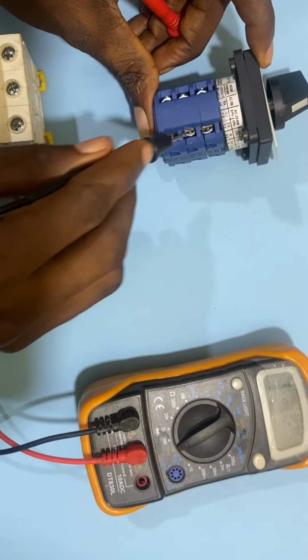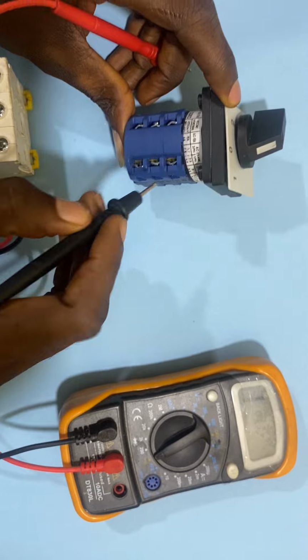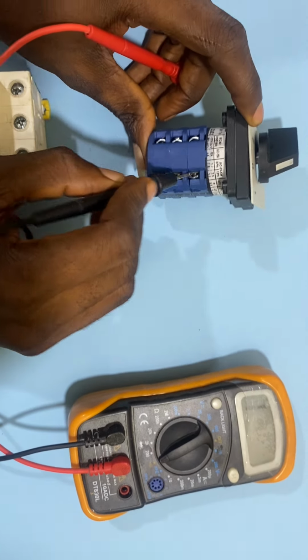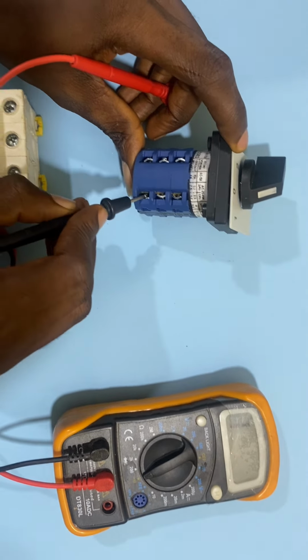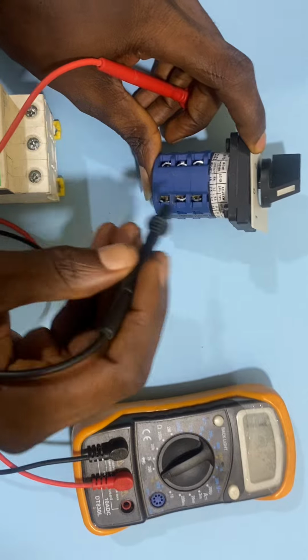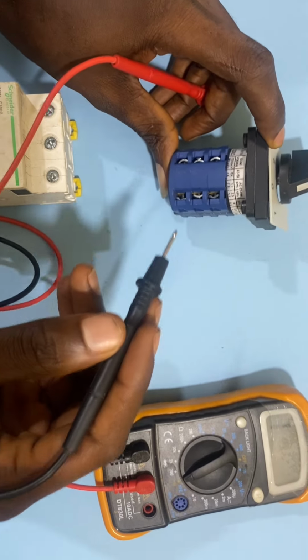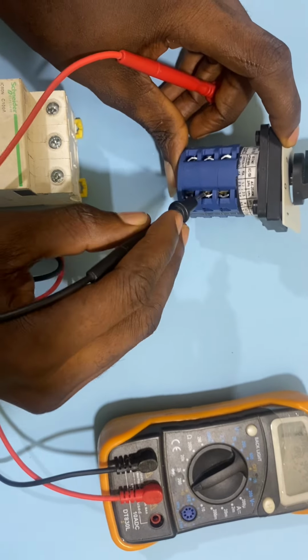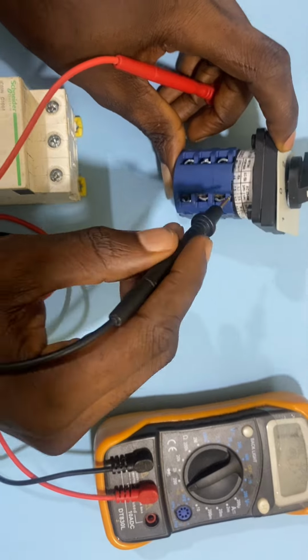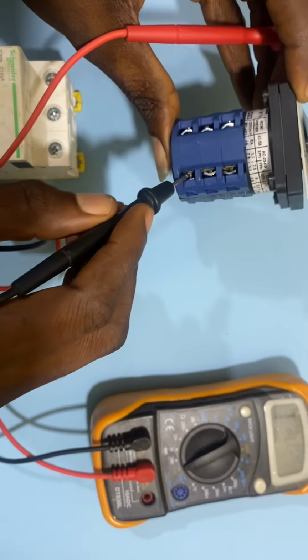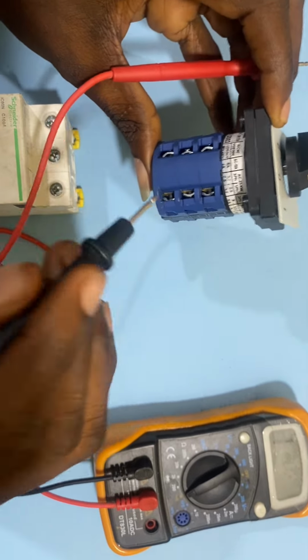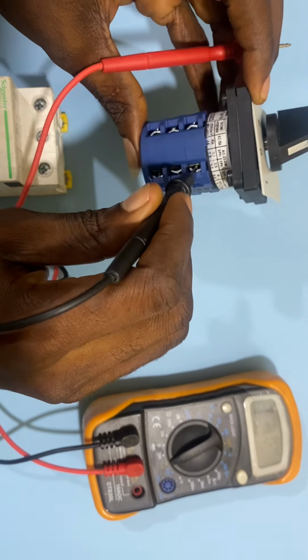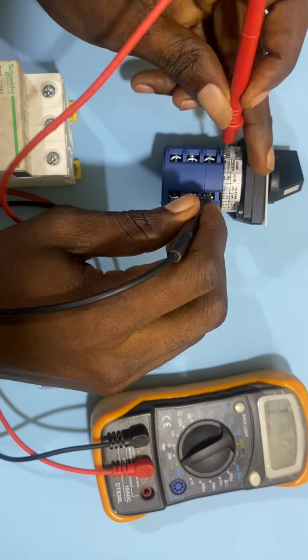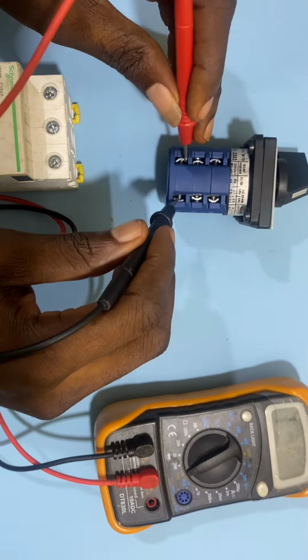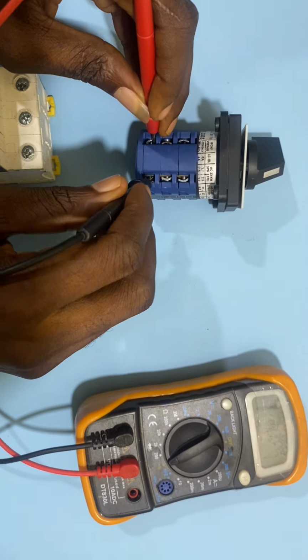The reason we have three is that this selective switch is a three-phase selective voltage switch. If it was single phase, you would have one, and if it was two-phase, you would have two. Now that it is three-phase, you can use a three-phase voltage supply. But in this case, I want to use only a single-phase voltage supply. So I will take this one to be my live supply wire, and I will take this one to be my voltage neutral.